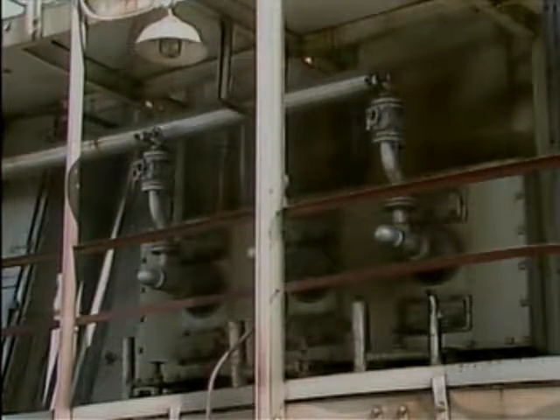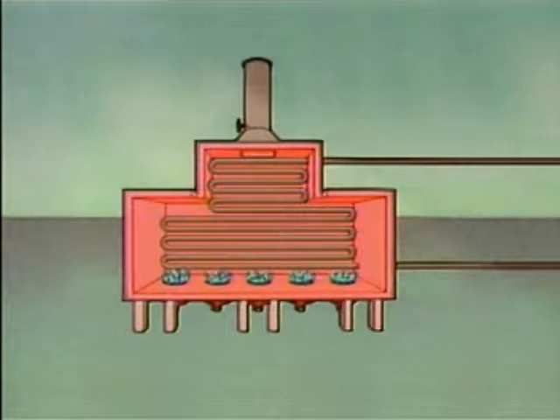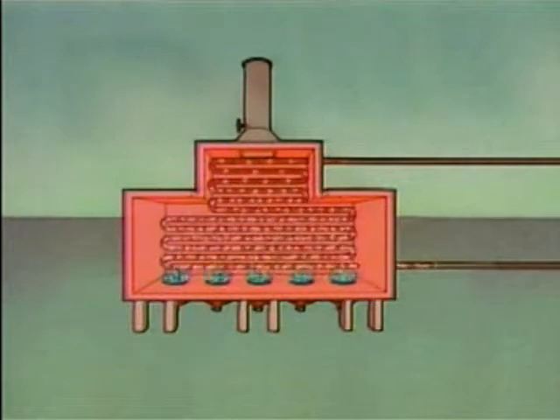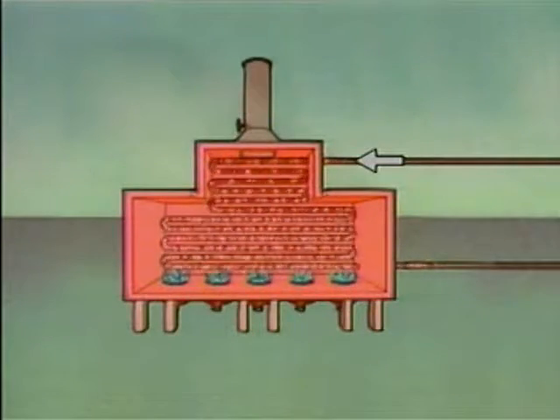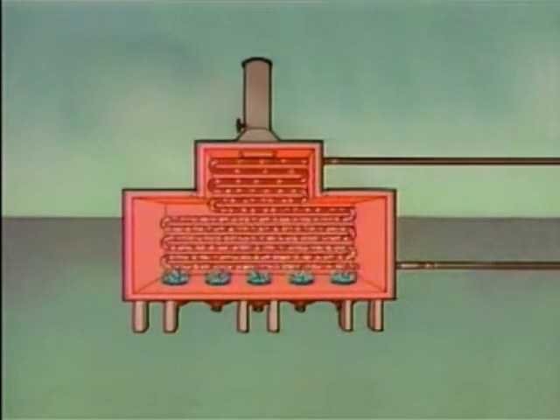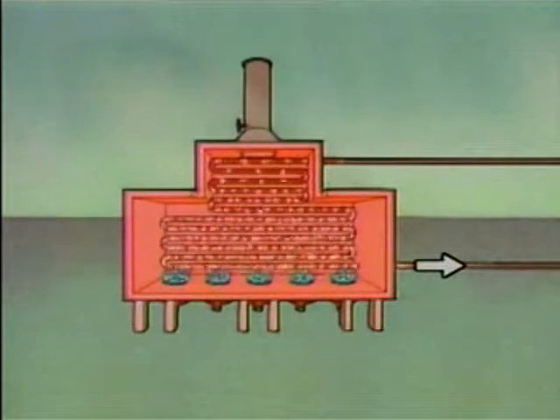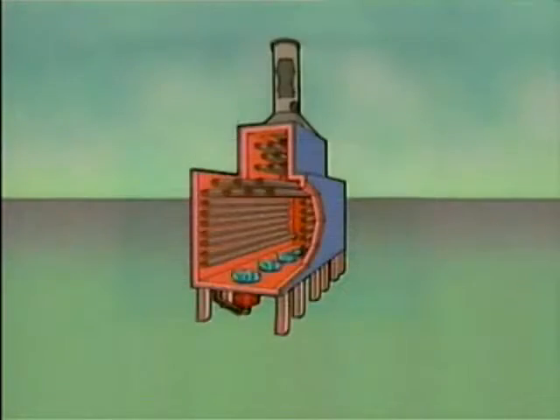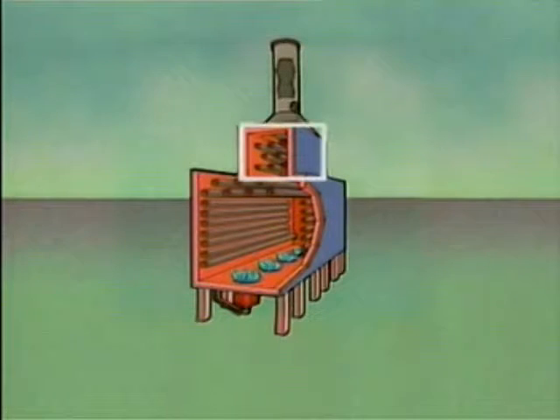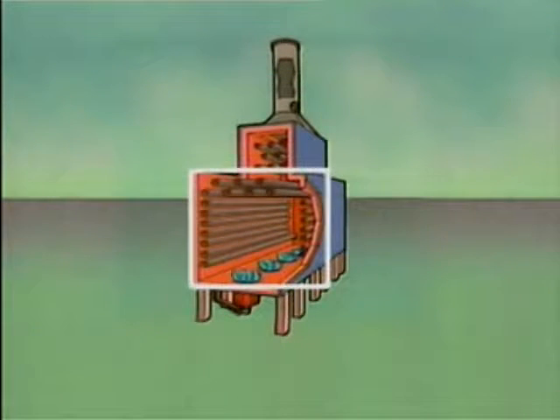Some furnaces are wall-fired, while others may use both wall and floor burners. In addition to burners, furnaces contain many other important parts. Inside this furnace, tubes carry the process fluid through the furnace. The process fluid enters the furnace in the tubes near the stack, passes through the tubes, and leaves near the bottom of the furnace by the burners. The tubes are grouped into two major areas: the convection section, which is closer to the stack, and the radiant section, which is closer to the burners.